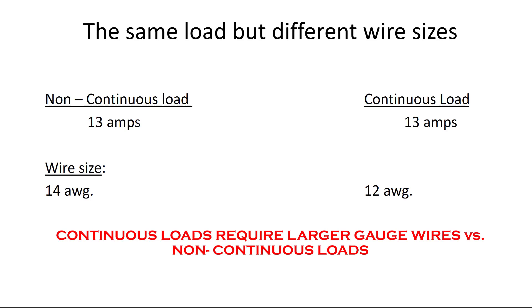If we have two loads — one continuous and one non-continuous — but they operate at the same value of current, the wire sizes will be different for the two loads. A non-continuous load operating at 13 amps only requires a wire size of 14 gauge, but a continuous load of 13 amps requires a 12 gauge wire.